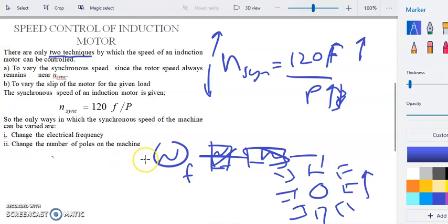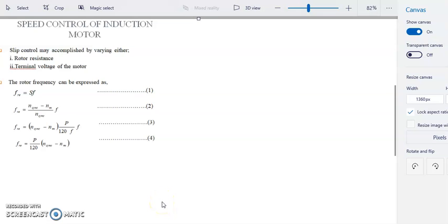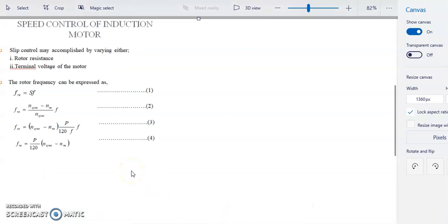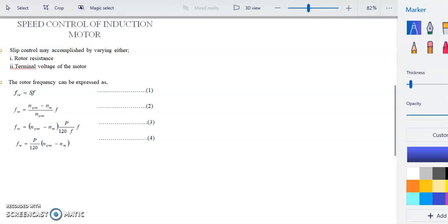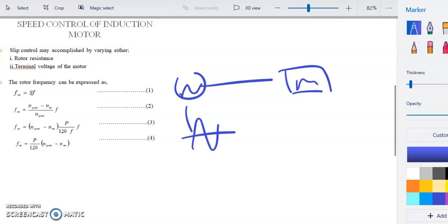Another kind of control to modify the speed of your induction motor is slip control. We can adjust the resistance of the rotor, like what we apply on the wound type induction motor, or we adjust the terminal voltage of the motor, the incoming terminal voltage, between your source and the motor. So you modify the magnitude of the source, and the lower the magnitude, the lower the torque and the lower the speed.